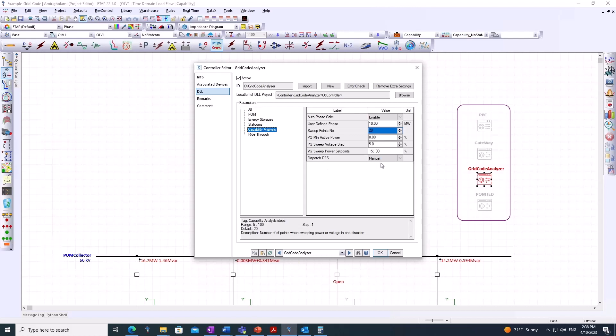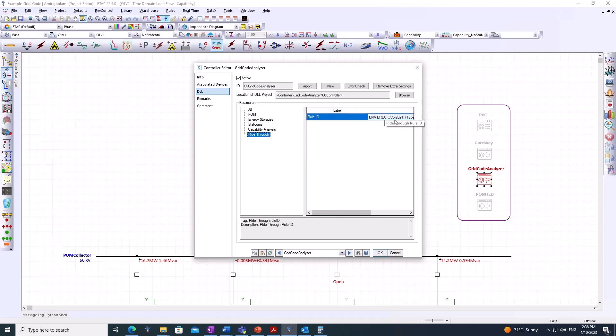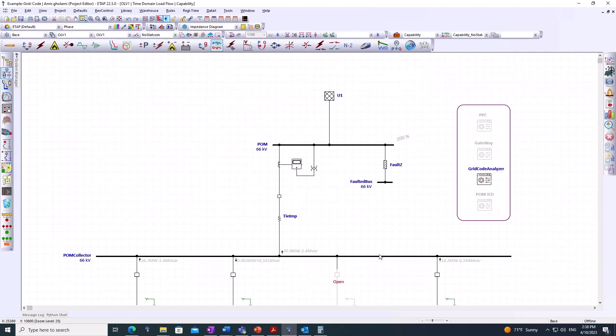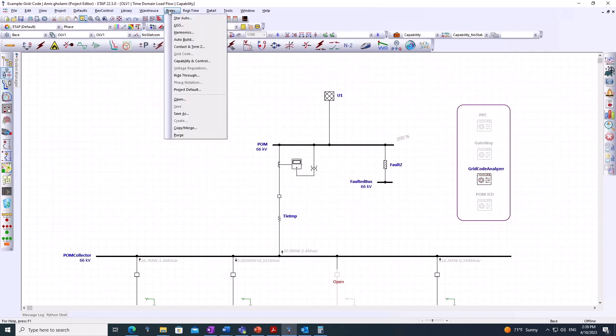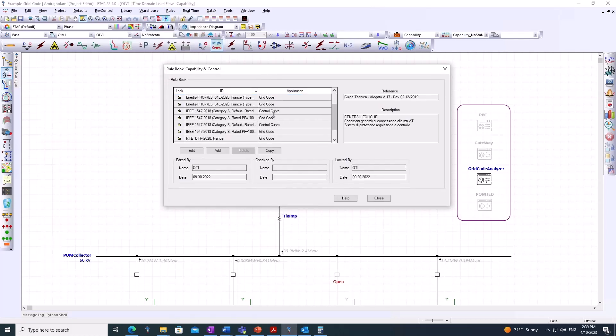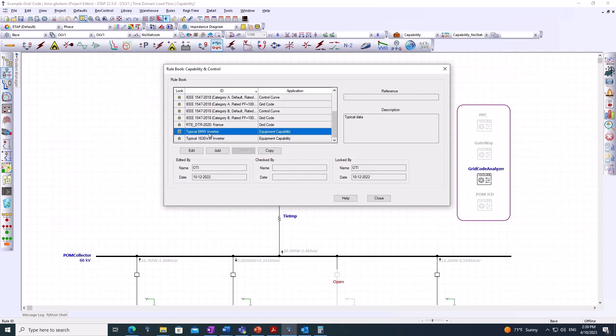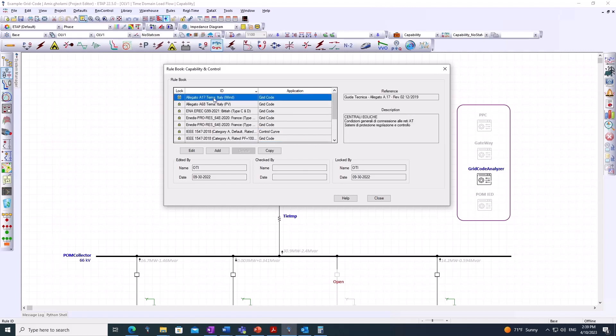The dispatch of energy storage systems can be either manual or auto. Manual means there is no command from the grid code analysis, while auto means it is considered as part of the power plant for grid code studies as well. The ride-through rule ID is defined for the ride-through studies of the power plant. Under the rules section, there is a capability and control area where the user can define their specific inverter capabilities as well as their grid codes.